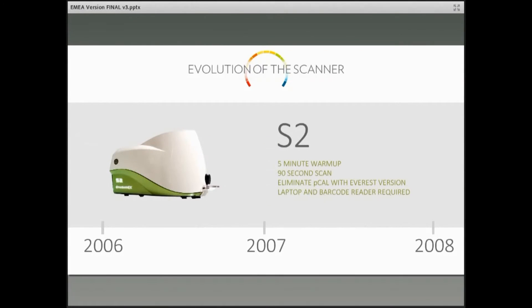The next evolution was really almost a revolution with the S2 scanner. On the S2, our goal was to make a Raman spectrometer that would be even smaller and more robust, less sensitive to temperature variations, and something that would be easier to calibrate. We worked to incorporate internal calibration standards so that you could eventually get rid of all the PCAL. That was a huge burden dropped off individuals that wanted to take this into their living rooms or wherever to help people measure their carotenoids. But the S2 scanner was still connected to a computer — there were wires — though it had a quicker warm-up and was certainly a lot more robust.